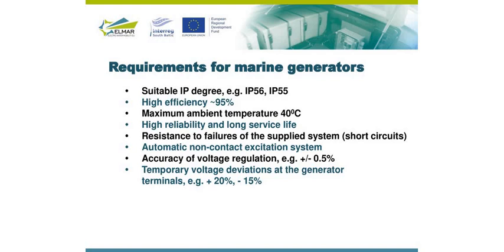There are different requirements for marine generators. They need to have a suitable IP code, for example, IP56, IP55. They need to have a high efficiency and need to withstand proper ambient temperature, for example, 40 degrees. It is also required to have a high reliability and long service life, and the generator needs to be proof on failures and short circuit, which can happen, and the automatic excitation system is now a standard.